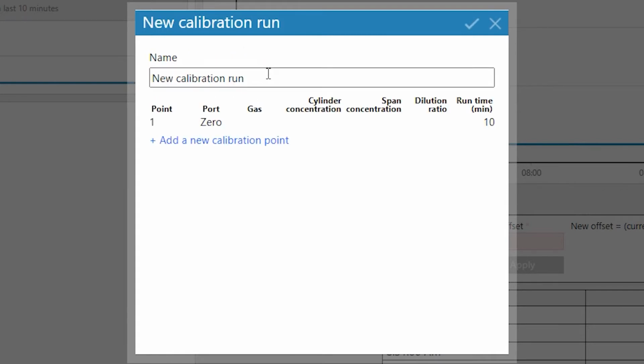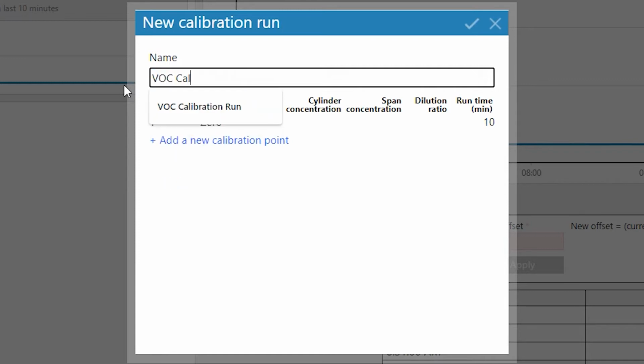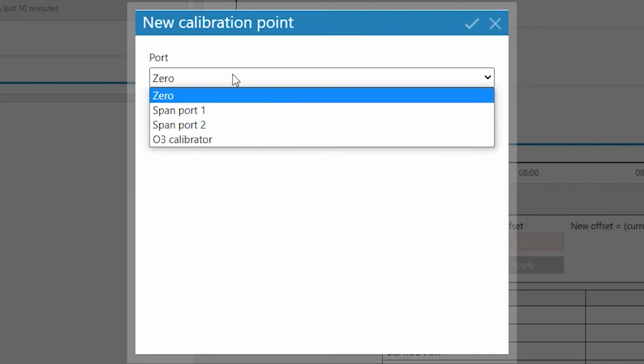If you're renting from us, this will just be called VOC Calibration Run, and you won't have to do this part. So just to show you how you start a new run, this is VOC Calibration Run. The first action we're going to do is to run some zero air through the monitor. We want to add another action, which is to run some isobutylene through the monitor.